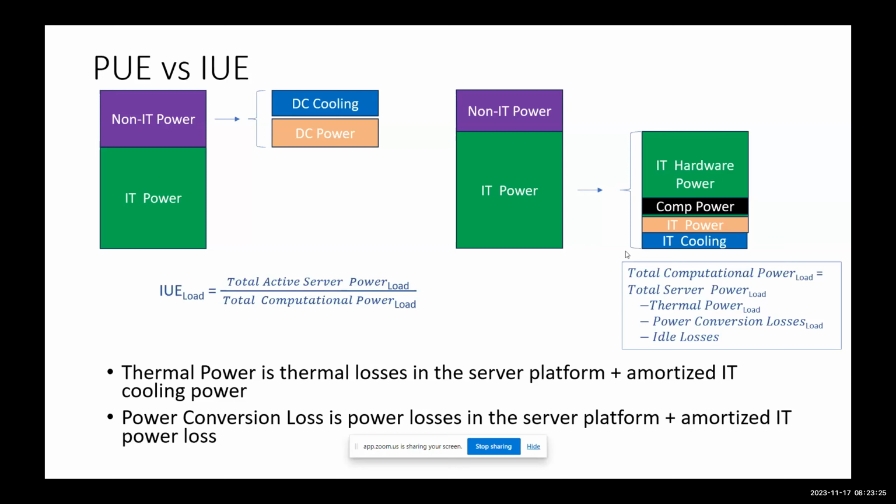So to me, all of this is manageable. To me, the hard problem is one of the things that PUE, by the way, to their credit, actually did too. PUE is also defined at load, except that nobody goes through that. If you read the Green Grid paper on PUE, they talk about load. When you say load, what does load mean in a rack full of servers is a hard thing to figure out, and that's where we need to spend our time.